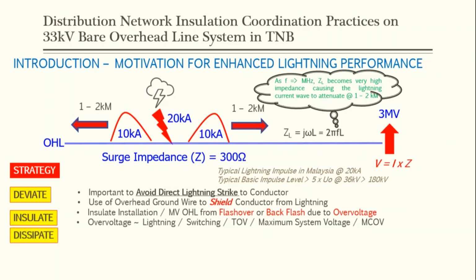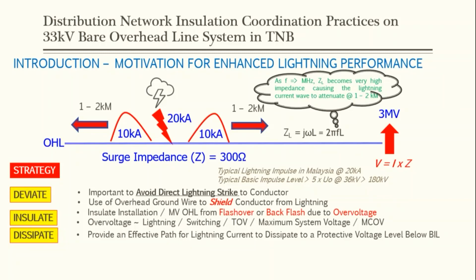Then we need to dissipate the lightning current. Why? To provide an effective path for lightning current to dissipate so that the protective voltage of the system will be below the BIL. For example, if we have a 170 kV BIL for our 33 kV system with a margin of 25%, we need to reduce the protective level, or the residual voltage, to maybe around 140 to 150, between 25% to 30% protective level or safe margin.